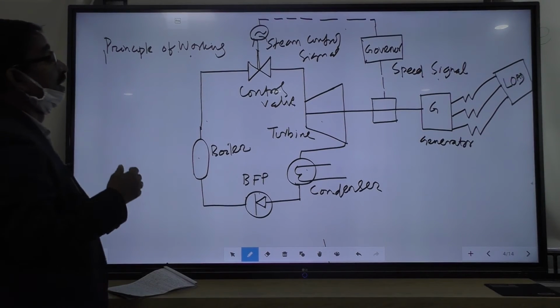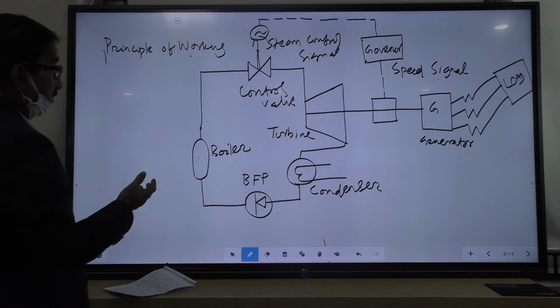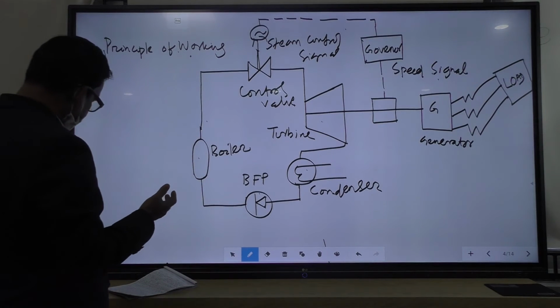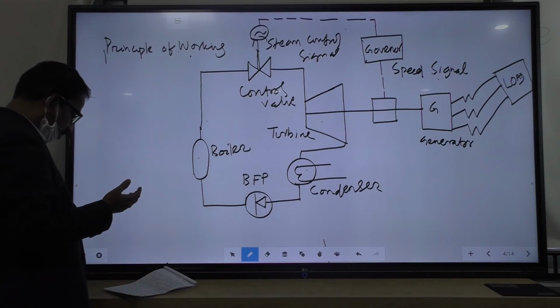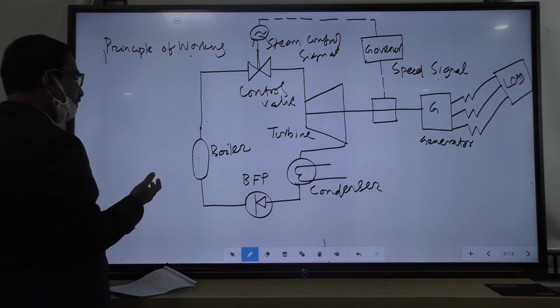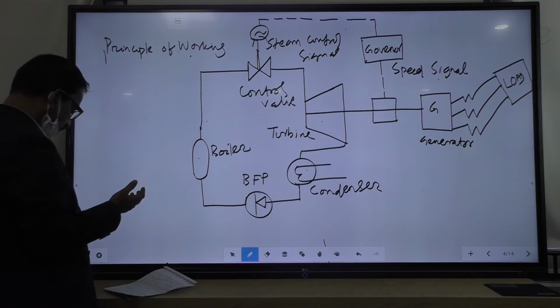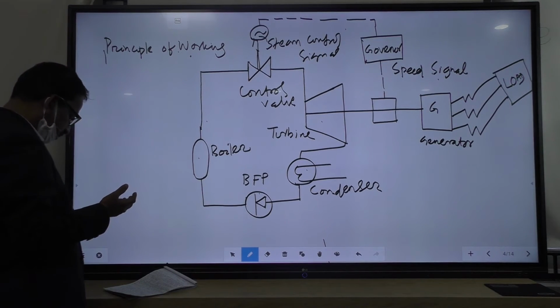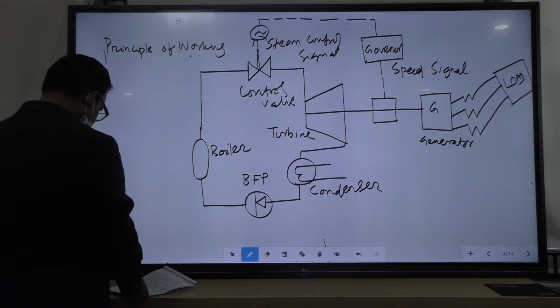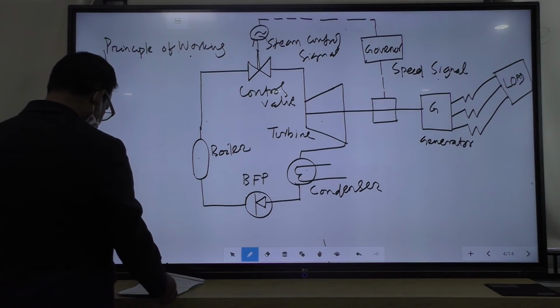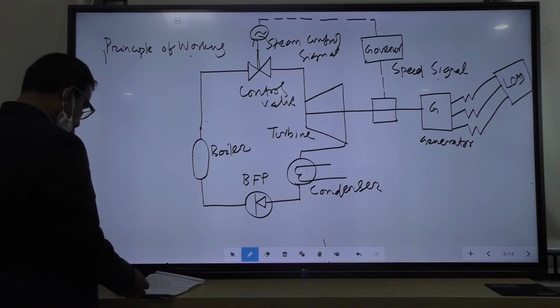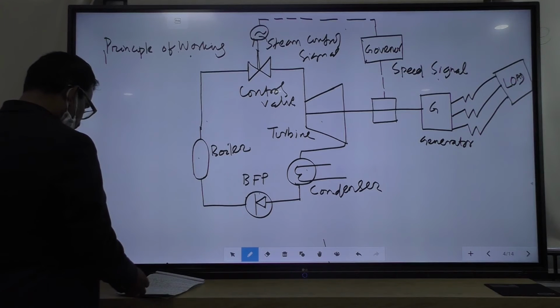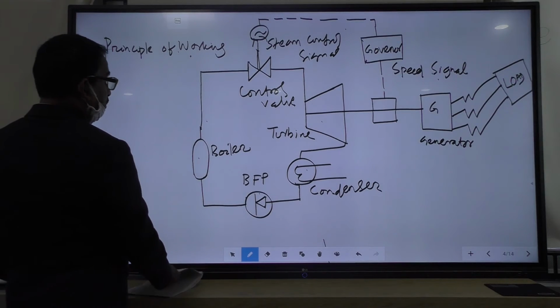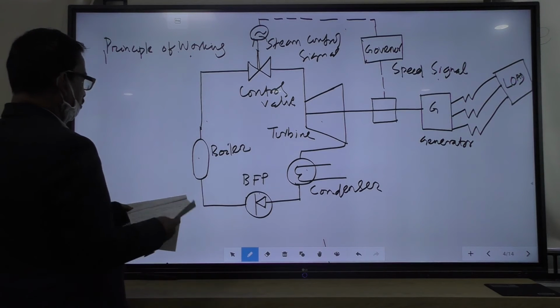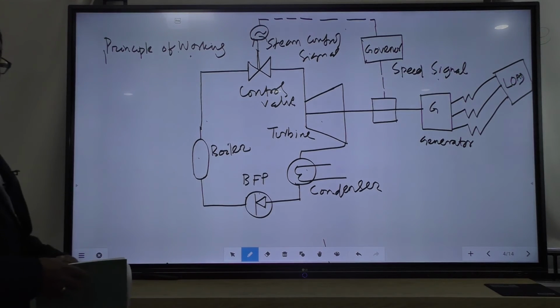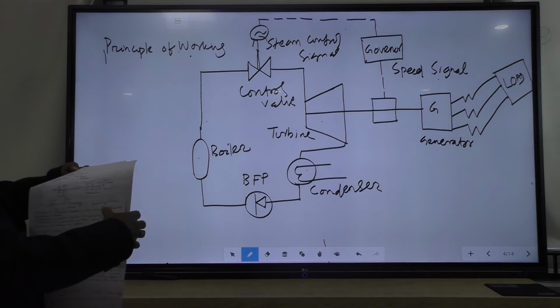If a machine suddenly stops or its load is lost, it will protect the machine from abnormal and emergency situations like overspeed trip and generator protection. So that is protected by the governor. Number 4 is to stop the turbine from normal rated speed condition to standstill. It can also stop the machine. The governor that starts the plant also stops the plant.